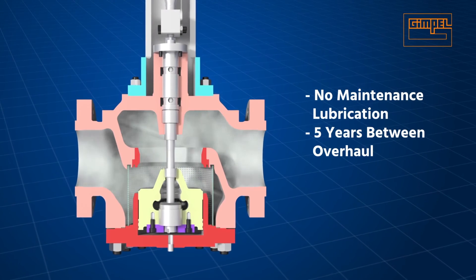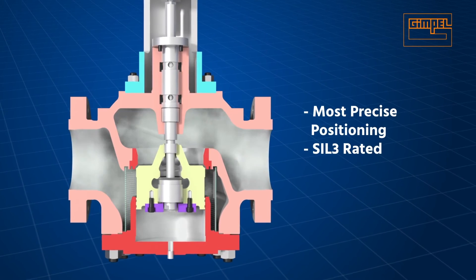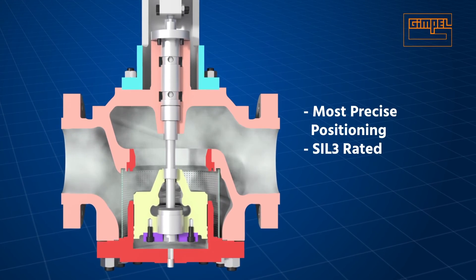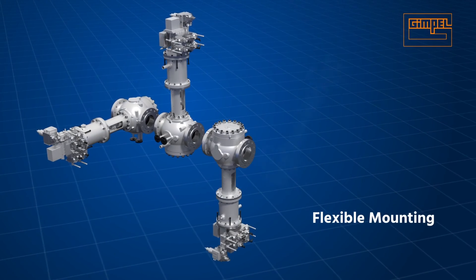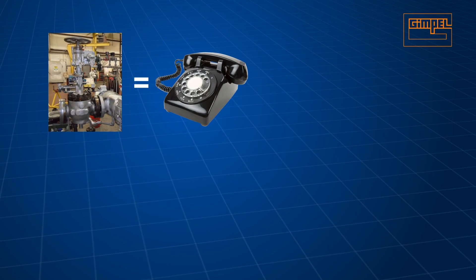Maintenance is reduced compared to mechanical latch, with no maintenance lubrication required. Time between overhaul is five years, as opposed to three years for mechanical latch. The EH TTV provides the most precise positioning and is SIL 3 rated, as are all Gimpel valves. The EH TTV design also allows multiple mounting configurations.